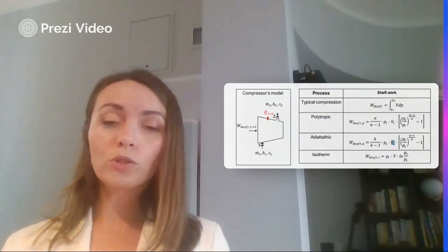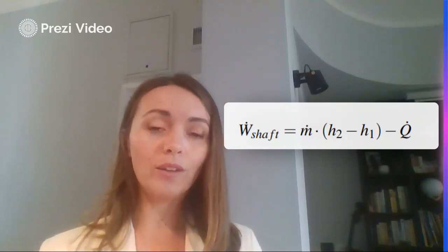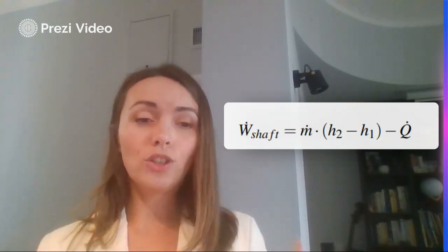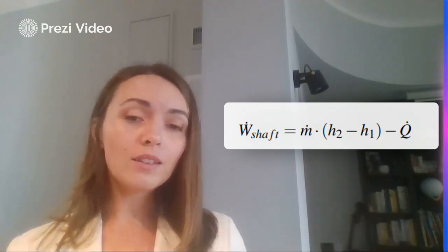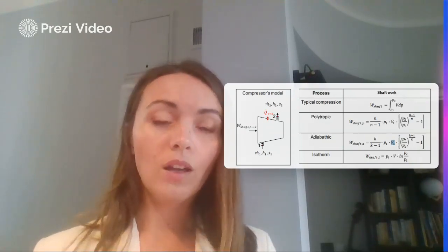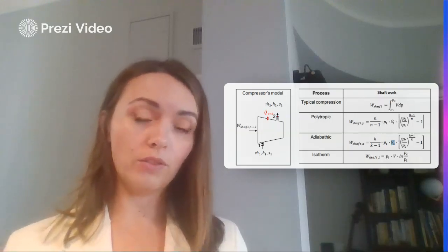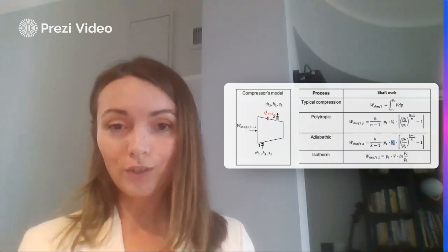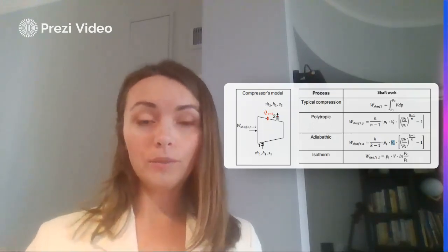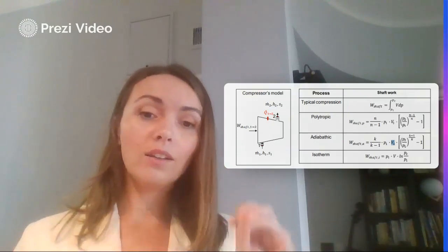Now we go to the compressor itself. The basic equation is: to calculate the full technical energy or shaft work, we need to understand that changes of enthalpy result in heat exchange and shaft work. To calculate the usable work done by the compressor, we take the polytropic system behavior and analyze the heat exchange as well. It is not simply that heat equals shaft work, because first, isothermal compression is not possible, and second, it is an open system where the work done by the shaft changes the enthalpy content inside the system, also resulting in heat exchange.